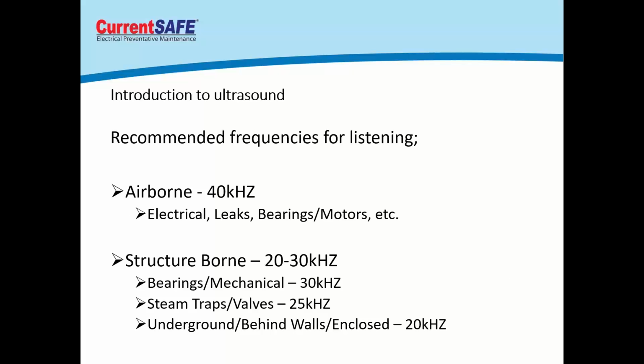For our technicians, I teach that airborne ultrasonic—for electrical leaks, bearings, motors, anything in the airborne realm—is typically in that 40 kilohertz range. They can tune the frequency of the ultrasonic probe based on what they're using it for. I teach them in class that for airborne, 40 kilohertz is where we like to tune it.